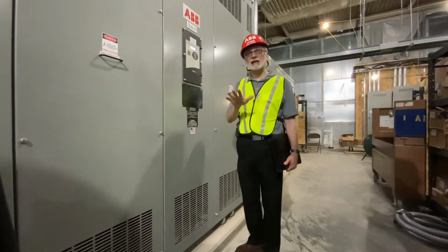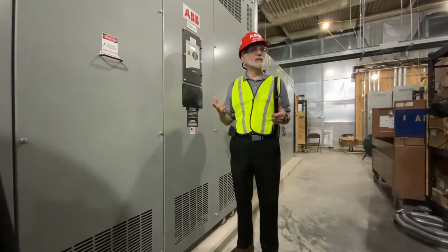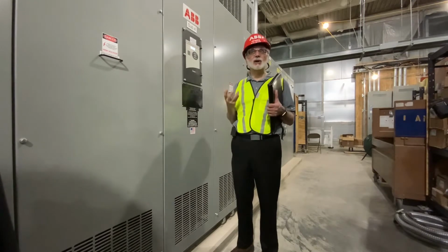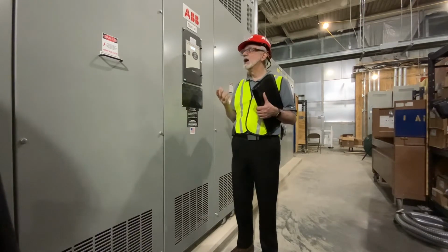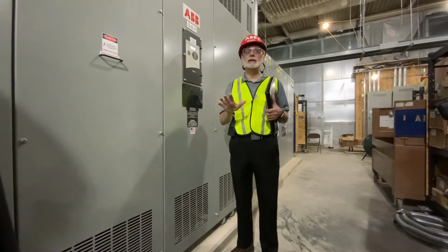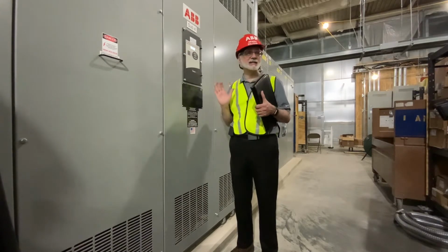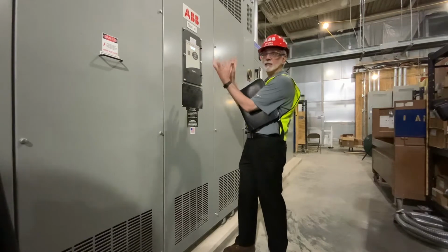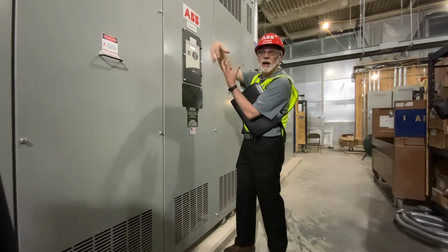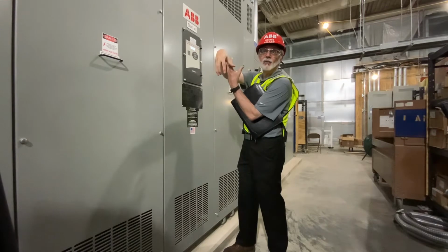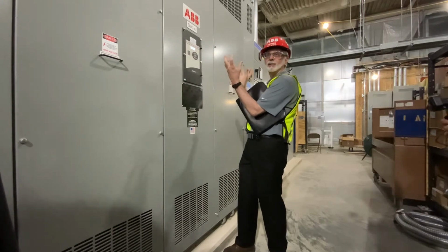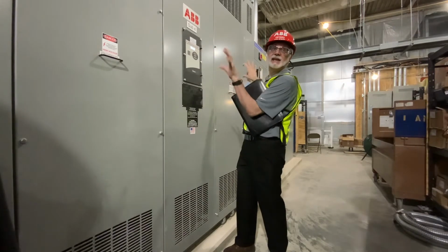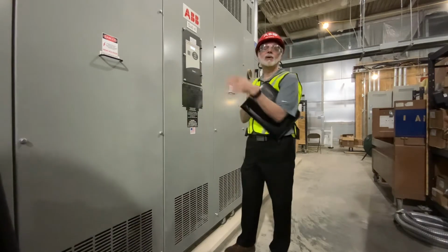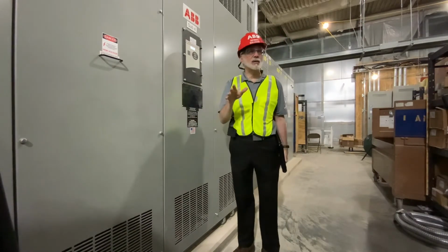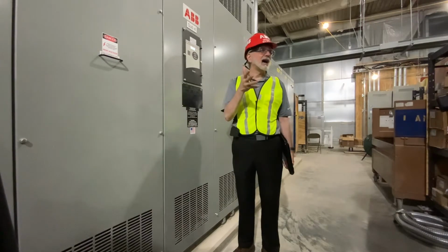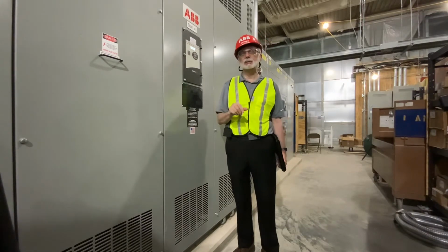One thing I will say is once the building gets a little bit more occupied and you start pulling more effective amps, it's not unusual for the B coil to run a little hotter than the A and the C. The reason is that the B is in the middle and it's got half of its coil blocked by one coil and the other half blocked by the other coil, where the A and the C have free air around them. So it is not unusual for the B coil to be slightly higher than the A and the C. That's nothing unusual.